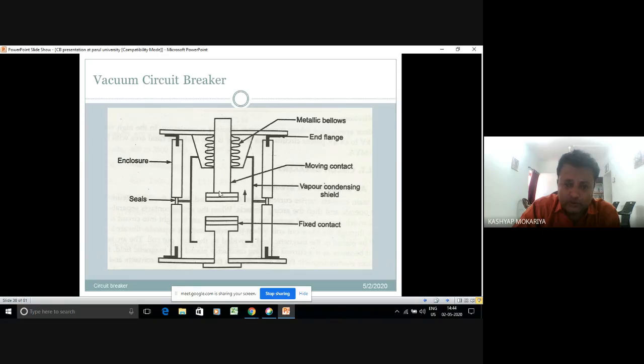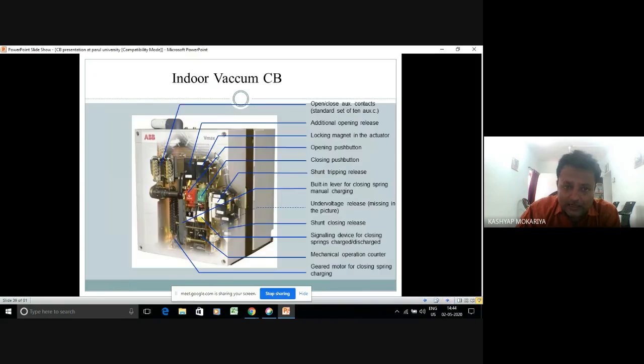The fixed contact is shown. This vapor shielding unit is shown. Now this is a closed assembly. From outside you can see a closed assembly. You can see the white bottles of vacuum. The level of vacuum is measured in torr. Generally it is 10⁻⁶ torr in VCB. So all those things are there. I have shown the front view.